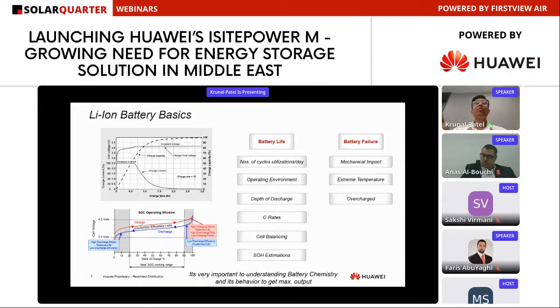If the battery is overcharged, that also leads to battery failure. Internal short circuit is another concern, because there are many modules and cells connected internally. In case of any short circuit between positive and negative, the protection system should be designed such that it does not lead to complete failure of the battery.